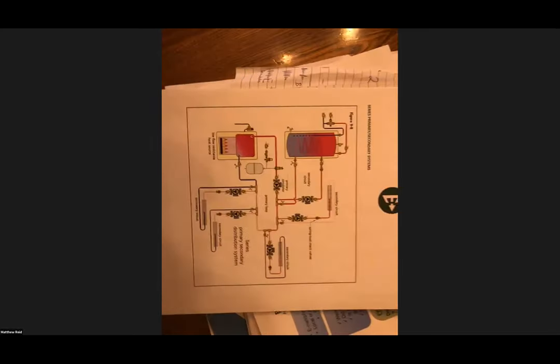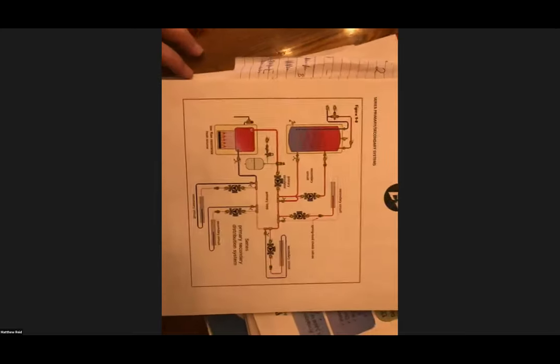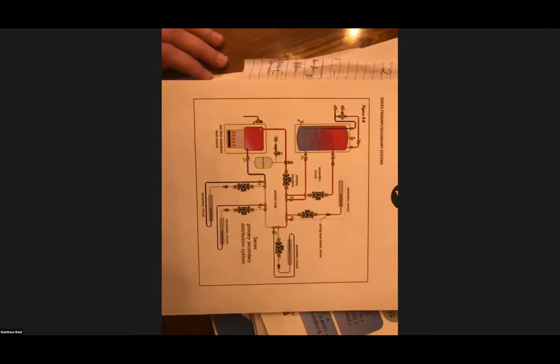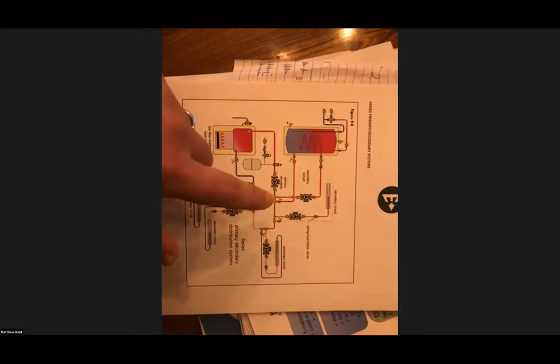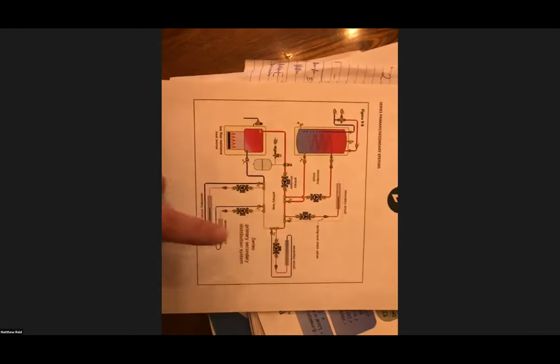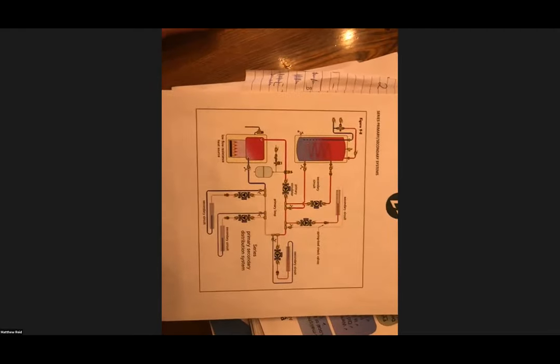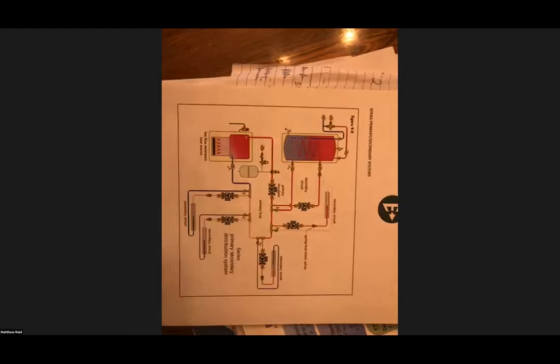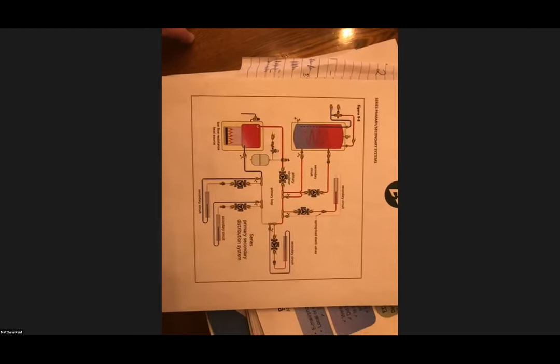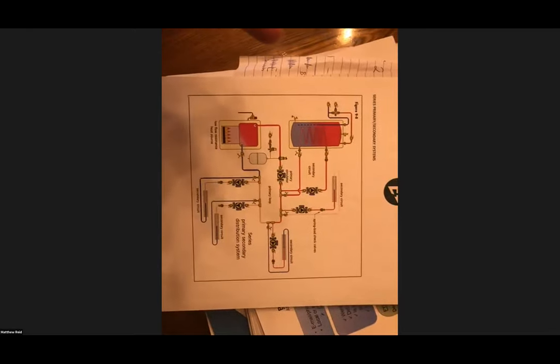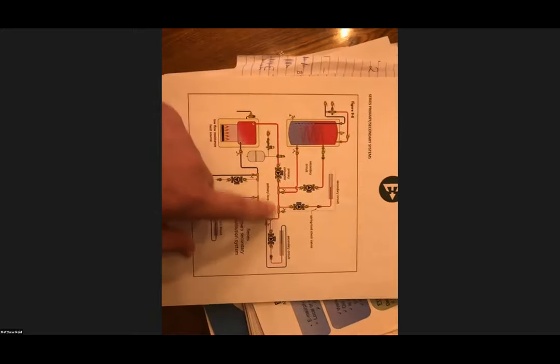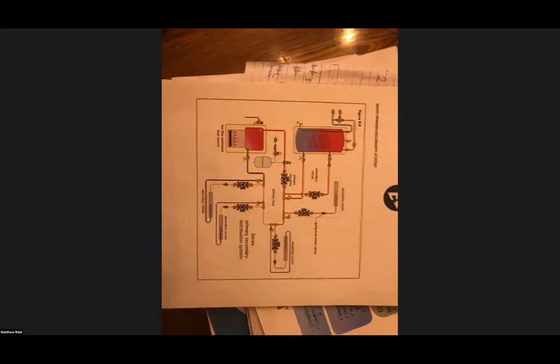Now, here we go. This is a much larger system. This is a primary secondary series, where we have our primary loop for our boiler, and then what we get out to is our hottest zones first, which is our indirects, our air handlers, and so on and so forth. Again, the temperature will drop as it goes on. So it does have its fallbacks or issues that it might have in the system, but it's still a fine way to pipe it. The boiler gets its primary loop as it's designed to, if that's the case for the boiler manufacturer, who wants to see primary, secondary. And then each zone is set with its own set of closely spaced T's to bring that water back and make sure that you get proper flow through your zone.